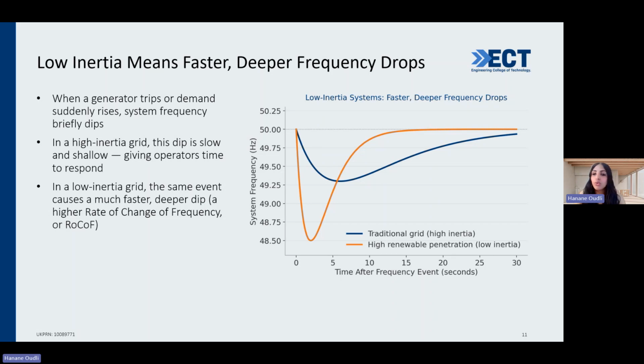The distinction matters because the first few hundred milliseconds, though this chart is for the first 30 seconds, after a disturbance can determine how much time different protection and control systems have to react. That's the difference between high inertia, traditional grid, and low inertia, inverter-based resources. It's time, because that determines how our protection and control systems have to react. So it's not only about where the frequency eventually ends up, it's also about how quickly we get there. That's why inertia is not just a theoretical machine parameter, it becomes a system-level reliability issue. This is also one reason why conventional planning methods alone may not be sufficient for every emerging grid condition.